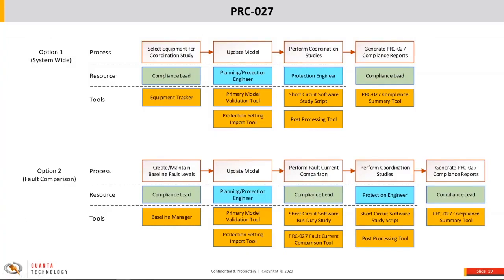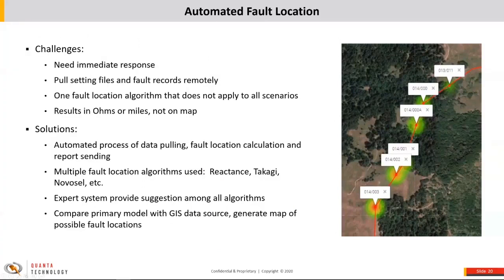There are two options for PRC-27. Option one is system-wide — you study everything BES in your system and produce a report. Option two is creating and maintaining baseline fault levels that limit your scope to only BES equipment with changes larger than your baseline, but it creates more issues in tracking and requires a strict process to be followed.